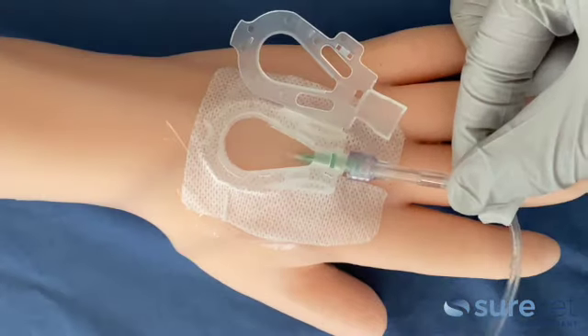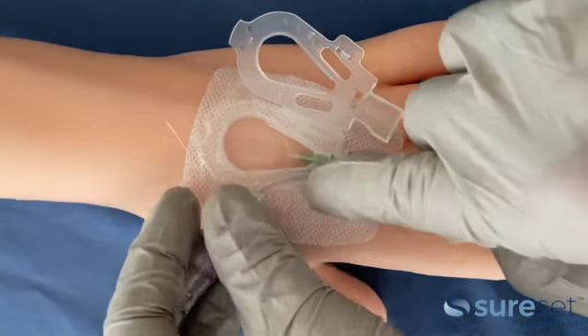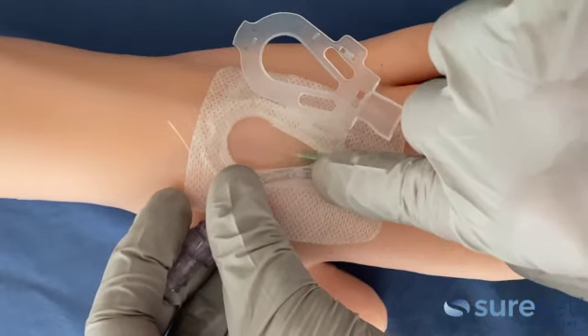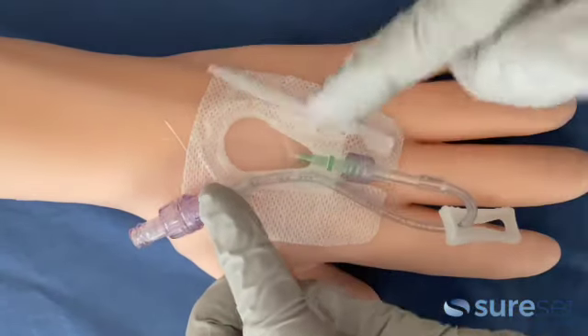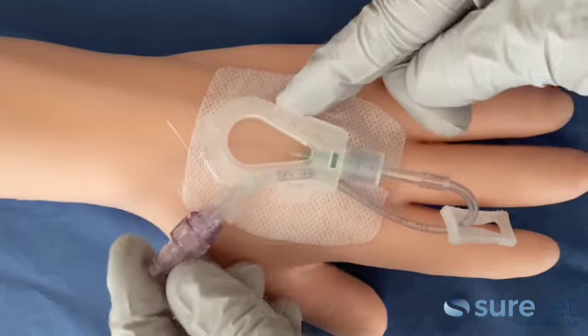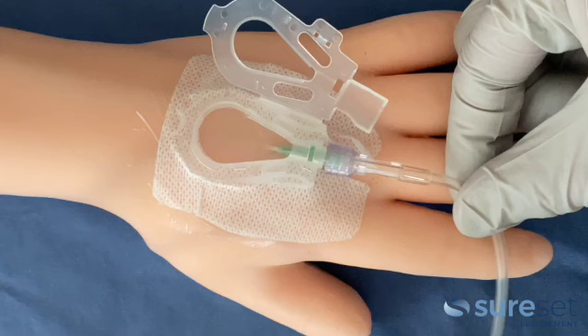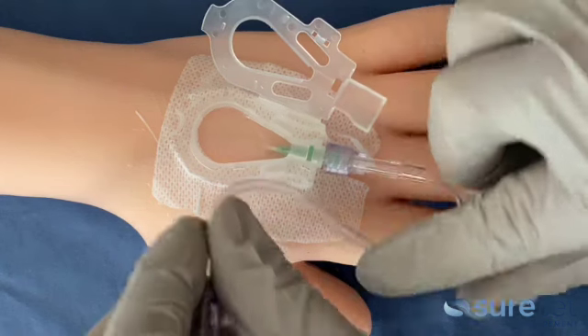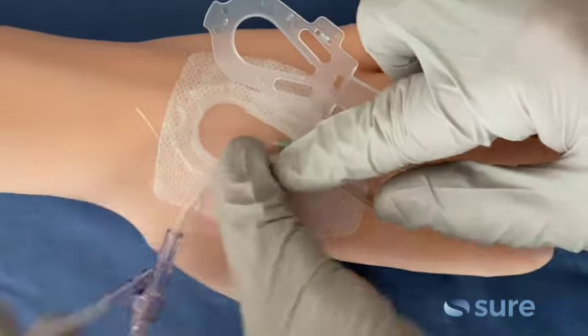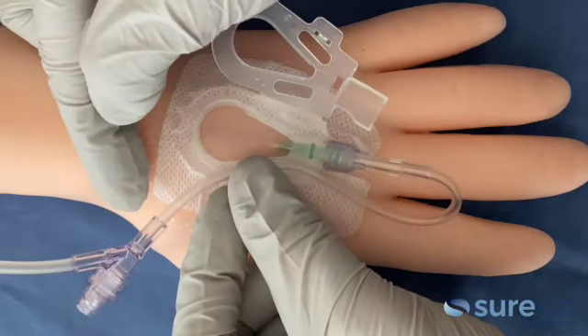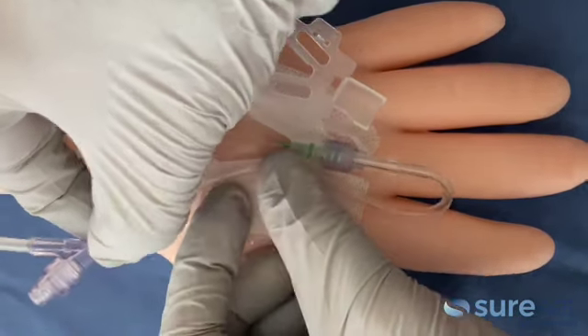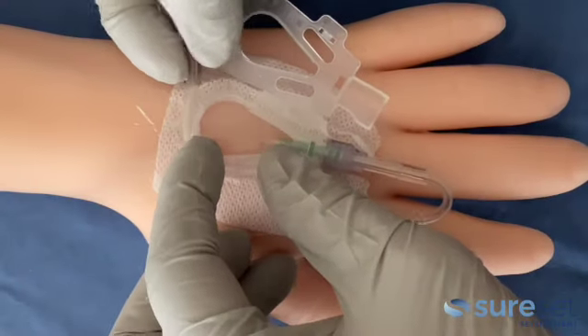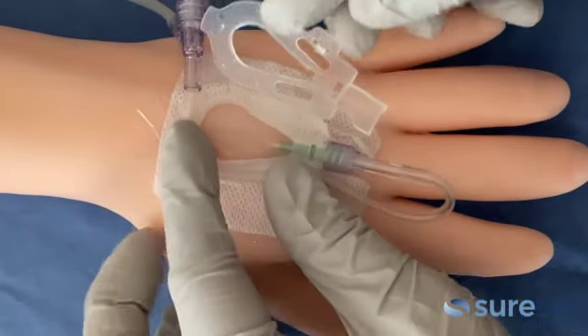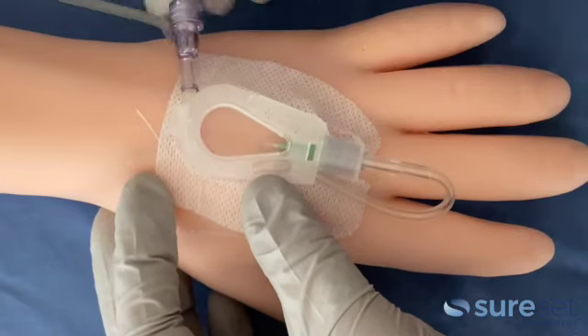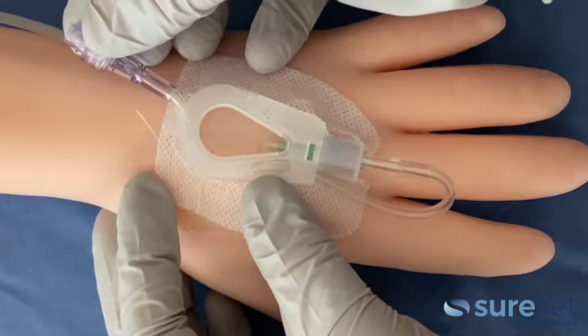The tubing can be placed in multiple configurations. Position A. In the first configuration, the IV tubing is positioned in the chosen channel and exits the device under the cover and on the same side as the lateral channel. Position B. If there is an IV extension set with more tubing beyond a short extension set, the clinical staff may desire the routing of the tubing using the apical channel toward the intravenous source or patient's antecubital area.